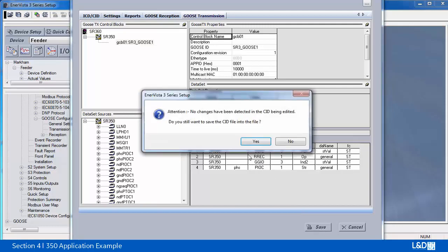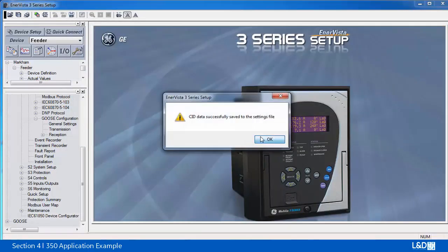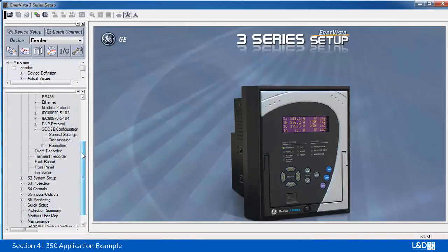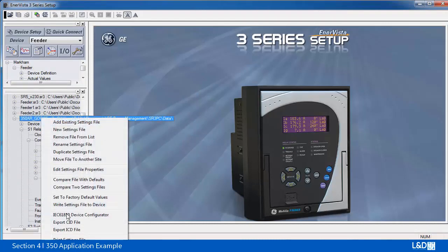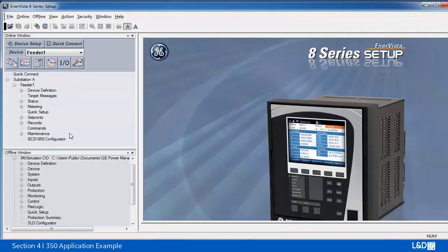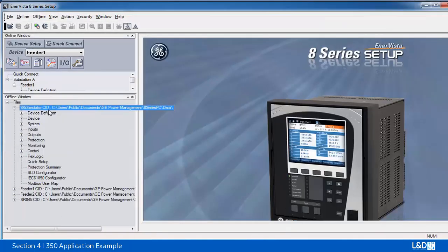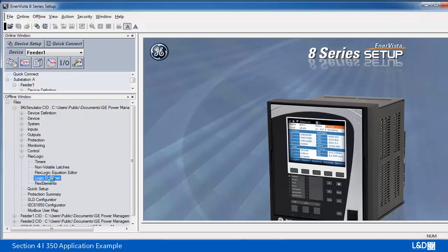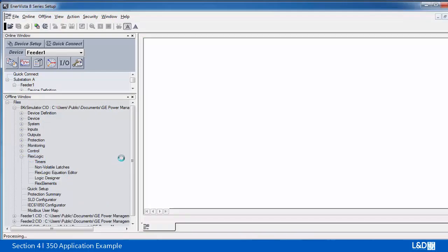So from the offline setting file, we can generate the CID file by right-clicking the offline setting file. We can choose export CID file, and this CID file will be imported into the 8 series. So now let's take a look at the 8 series. In the 8 series, we have a file called breaker simulator. Under this file, we first need to configure the flex logic, the logic designer. We're using 4 remote inputs.